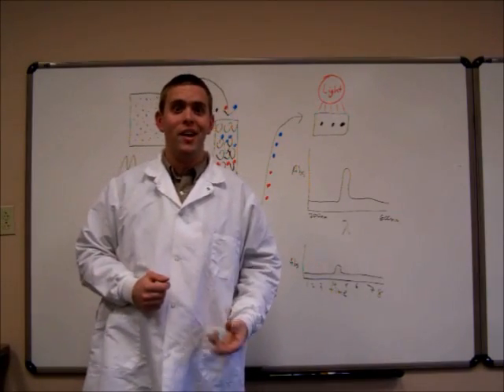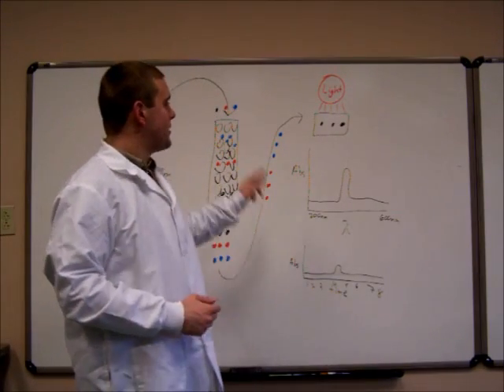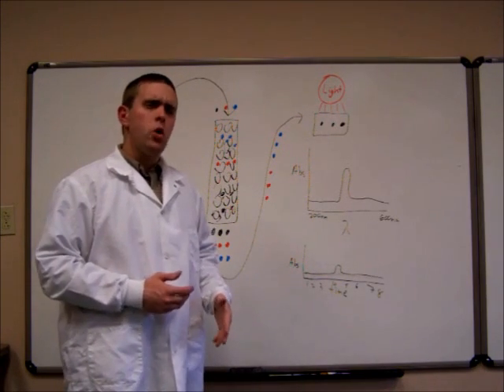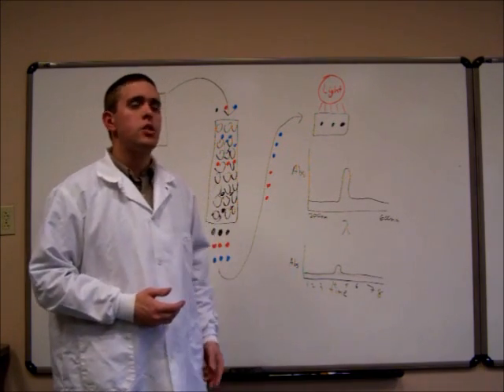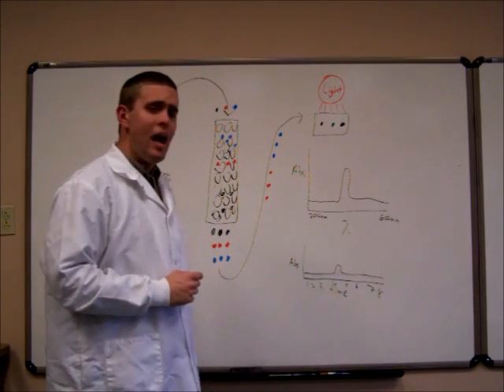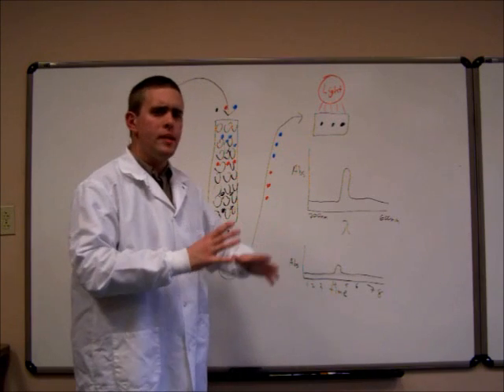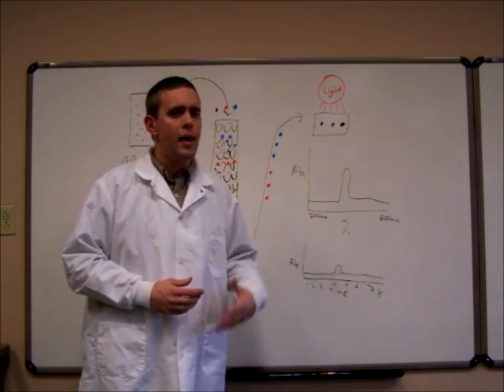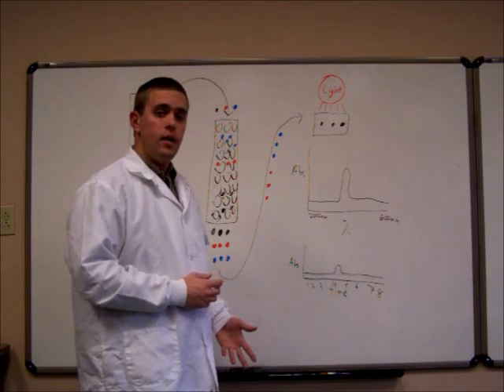Boy, I'm getting pretty good at this. Anyway, as the compounds enter the PDA, the light is shown through them. Now, this whole process, this analytical process, is called spectrophotometry. In spectrophotometry, we're looking for absorbances of the different compounds. We're looking for where the compounds will absorb light. So anyway, the graph is generated on the main screen from showing different parts of the visible and ultraviolet spectrum.